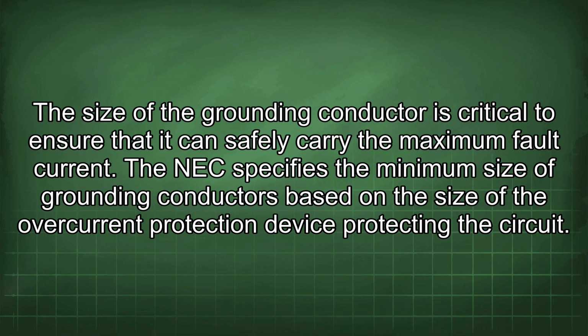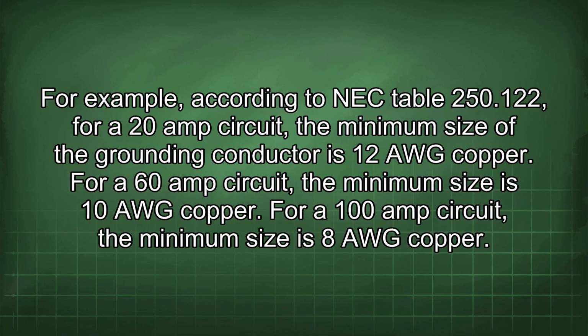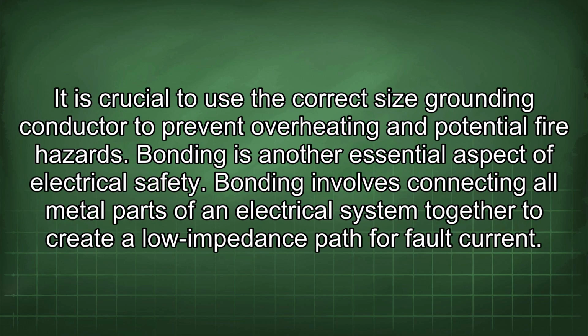The NEC specifies the minimum size of grounding conductors based on the size of the overcurrent protection device protecting the circuit. For example, according to NEC Table 250.122, for a 20 amp circuit, the minimum size of the grounding conductor is 12 AWG copper. For a 60 amp circuit, the minimum size is 10 AWG copper. For a 100 amp circuit, the minimum size is 8 AWG copper. It is crucial to use the correct size grounding conductor to prevent overheating and potential fire hazards.